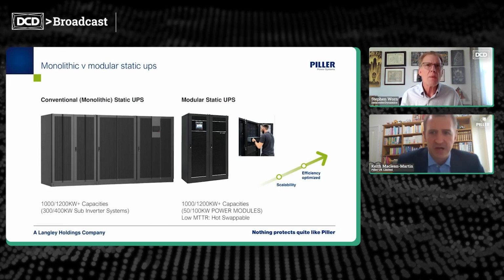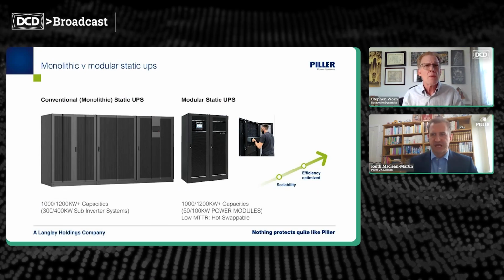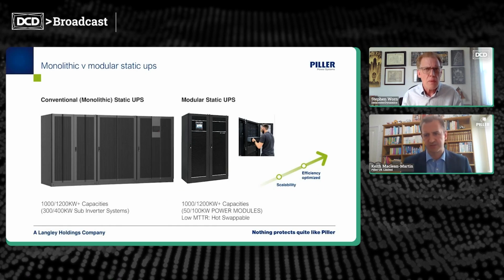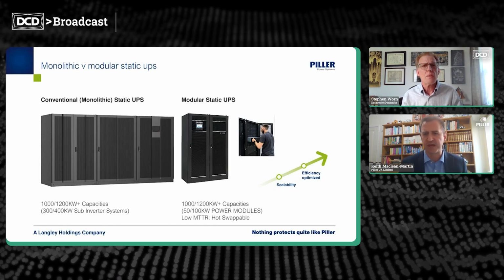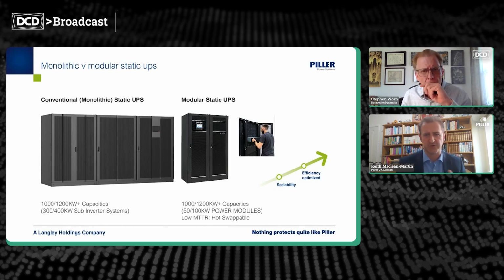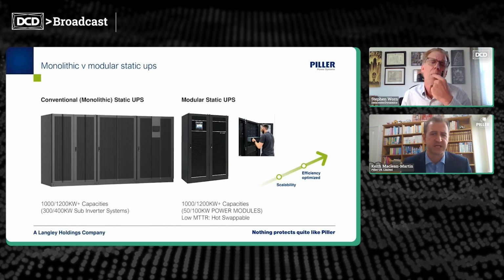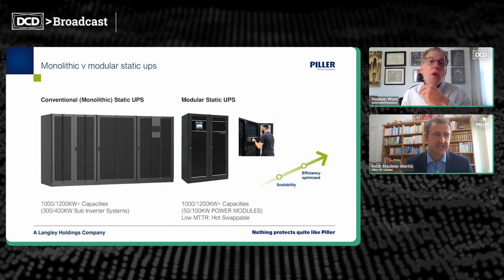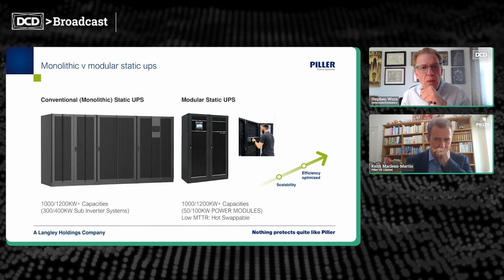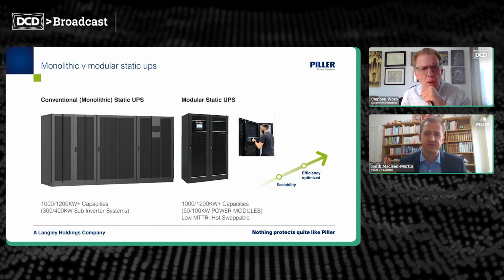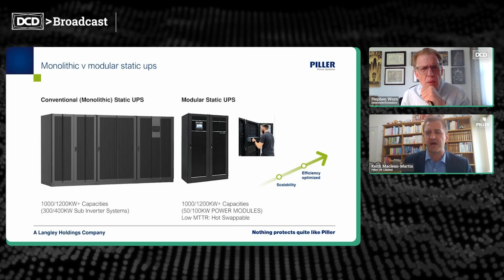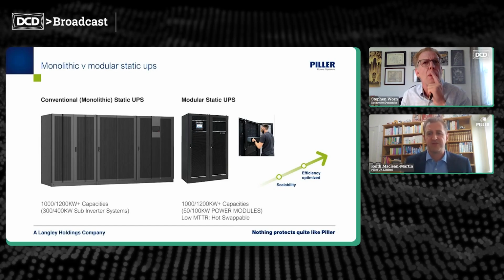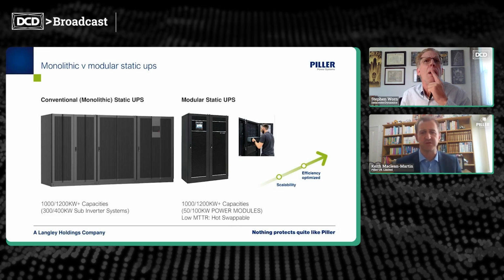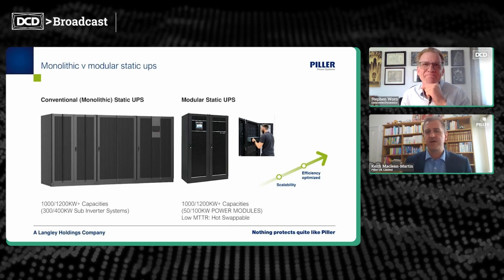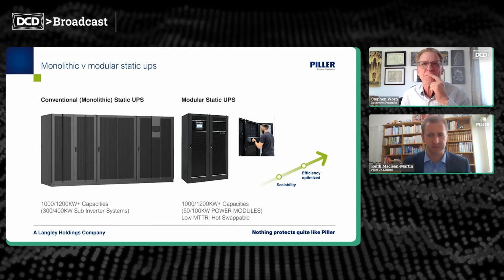Now, conventional or monolithic static UPSs have fixed capacities and are not easily scalable without parallel modules. Typically fixed at 1,000 or 1,200 kilowatt capacities, built up of non-redundant 300 or 400 kilowatt inverter assemblies. Now, with limited flexibility, efficiency optimization versus load demand is typically not possible. So for equivalent sized modular UPS, these are typically made up of 50 or perhaps 100 kilowatt power modules that are easily scalable from the initial stage to the future load demands and can also deploy flexibly to achieve the operating efficiency optimization.